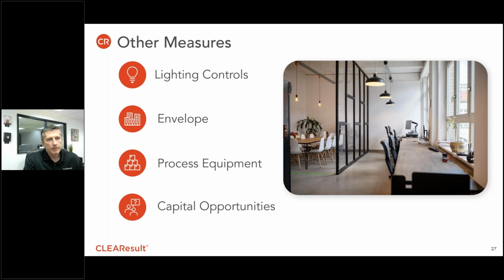HVAC measures are not the only measures looked at in a retro-commissioning process, although they are the primary ones we focus on. There are other measures to consider, particularly lighting controls where that functionality exists—we want to optimize those. The building envelope could be considered too, to ensure pressurization is adequate and infiltration is minimized. And if the building has significant process equipment, that could be looked at as well.